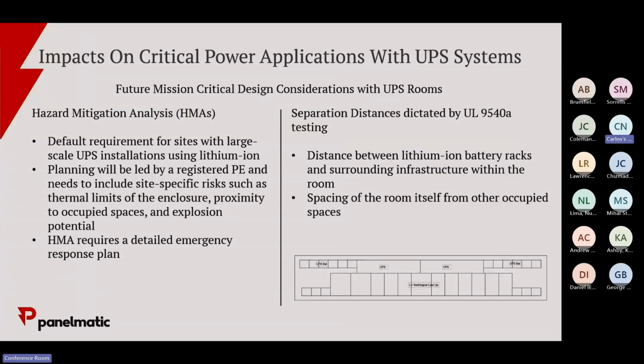Is the 3 foot off the backside, not around each cabinet? Yep, it's off the back. So once you start putting the batteries side by side, you're okay, but from the set of batteries itself in the first rack, you need 3 feet.